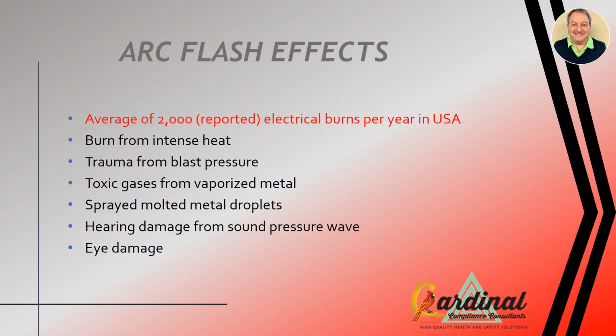The effects of arc flash, we have about 2,000 reported electrical burns. Some of the OSHA data is okay. OSHA's changed their reporting systems, and of course the 300 systems going back for major employers is changing. As we go forward, we'll get better data, but from what we can tell right now, about 2,000 people a year are getting burned. And the burns can be from intense heat, or they can actually be an electrical burn. Remember, I said that arc flash is electrically energized. Also, people are getting hurt from that pressure blast.